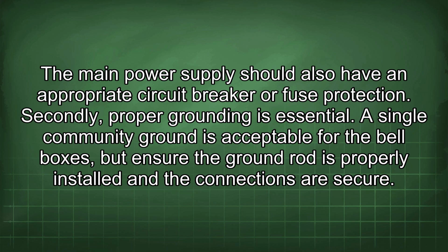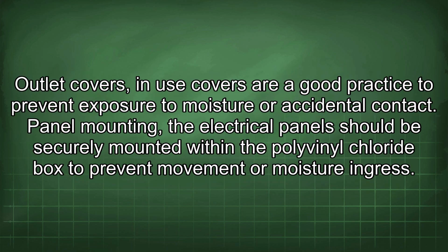Secondly, proper grounding is essential. A single common ground is acceptable for the bell boxes, but ensure the ground rod is properly installed and the connections are secure. Outlet covers and in-use covers are a good practice to prevent exposure to moisture or accidental contact. Panel mounting. The electrical panels should be securely mounted within the polyvinyl chloride box to prevent movement or moisture ingress.